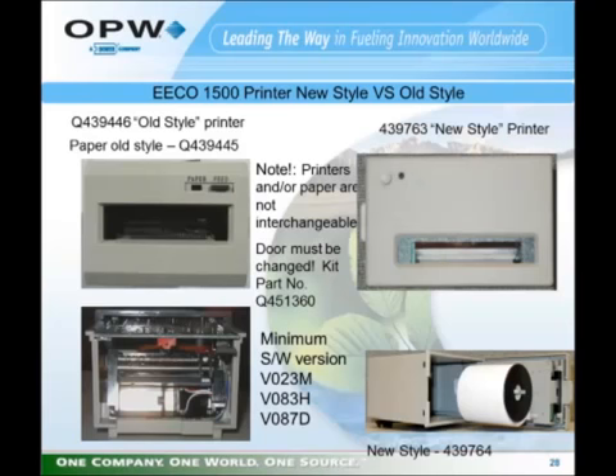The new printer is not fully backwards compatible with the EECO 1500. If the software in the EECO 1500 is too old, what will happen is any printouts on the new printer will, instead of starting at the top of the paper and printing down, start at the bottom of the paper and print up. So if your EECO 1500 is equipped with software versions prior to version 23M, version 83H, or version 87D, that's what's going to happen to you. You will need to upgrade your software to a later version in order to have the printer print from the top down.